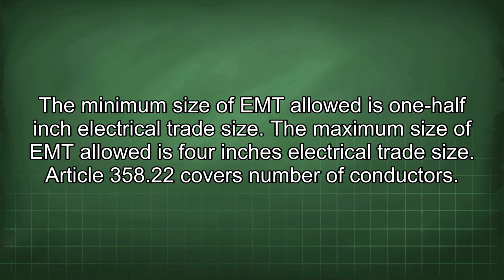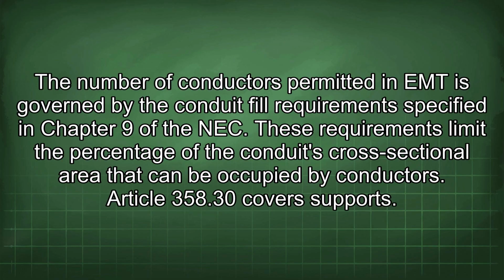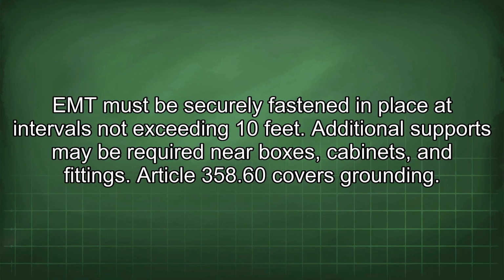Article 358.22 covers number of conductors. The number of conductors permitted in EMT is governed by the conduit fill requirements specified in Chapter 9 of the NEC. These requirements limit the percentage of the conduit's cross-sectional area that can be occupied by conductors. Article 358.30 covers supports. EMT must be securely fastened in place at intervals not exceeding 10 feet. Additional supports may be required near boxes, cabinets, and fittings.